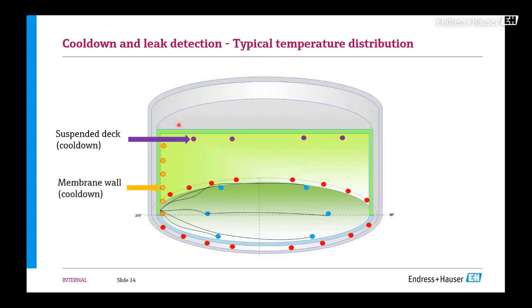You also have the membrane wall here, still inside the tank, and what we call the membrane bottom. So here you can see all those points. Again, depending on the size it will vary, and it also depends on the preference at the design stage, how many points you want to put inside. Those installed inside the tank are used for cool down and also for process monitoring of temperature when the tank is in operation.